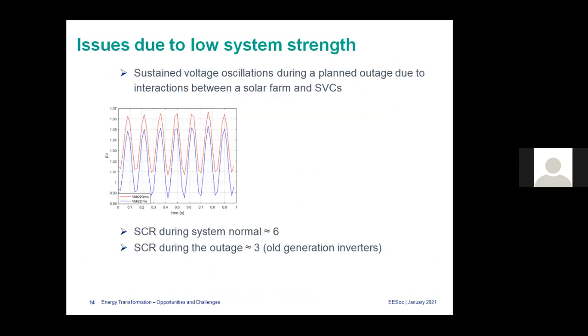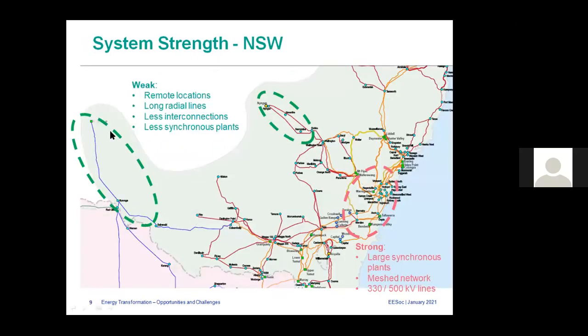Yeah, so these are a few practical issues that we have come across in low system strength areas. One is sustained voltage oscillations. For example, this happened during a planned outage where under system normal, the SCR is about 6. But when you take out one line, this is actually in this system. I will show you the location. Here, near Broken Hill. There is one 260 kilometer line from Buronga to Broken Hill, and then another line to Buronga, two 220 kV lines. So this line was out of service.